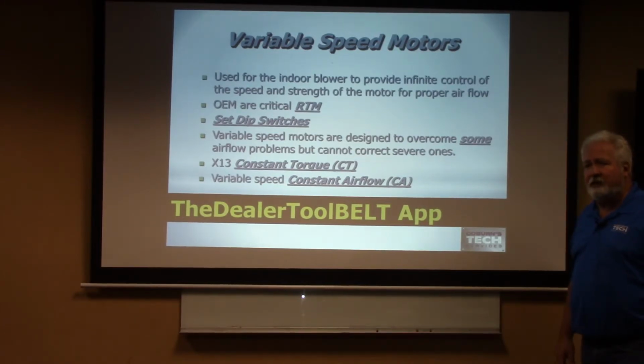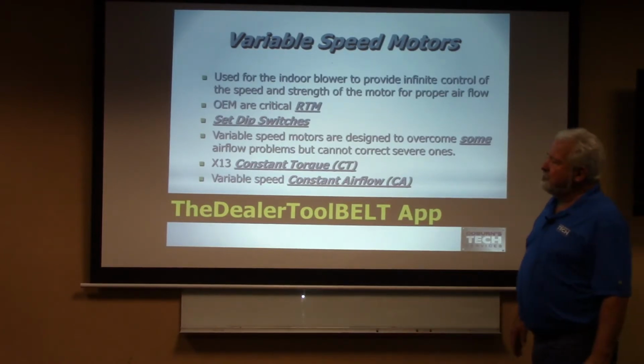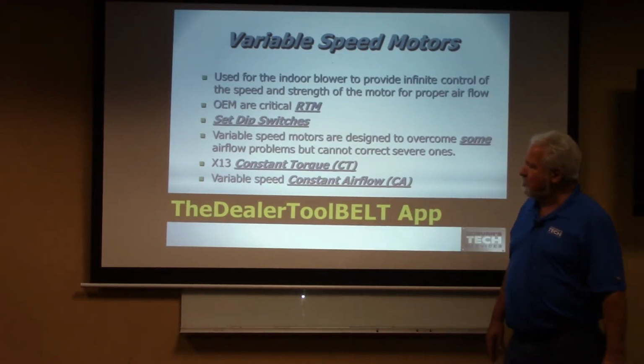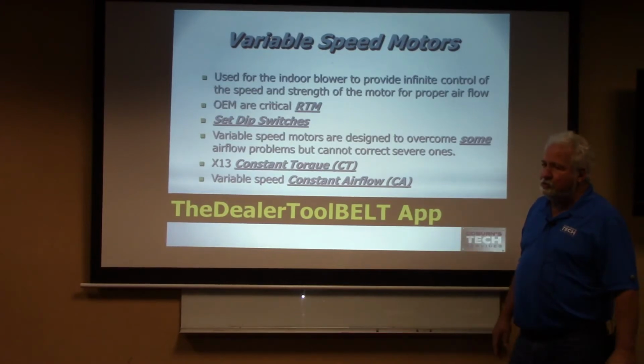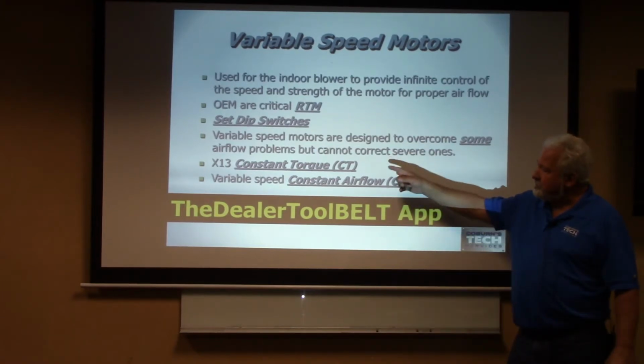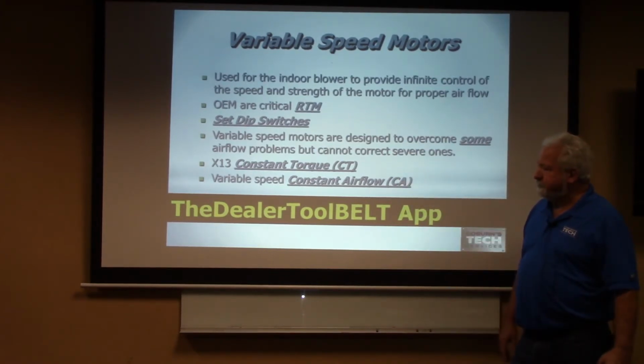Don't say, oh well, I've got a crappy ductwork system, so I'm going to put a variable speed motor on it and make it work. It'll just destroy that motor. There's X13 motors, they're called constant torque motors, and there's variable speed, which is true variable speed. They're called constant airflow motors. Understand that there's a difference, okay? Constant torque and constant airflow.